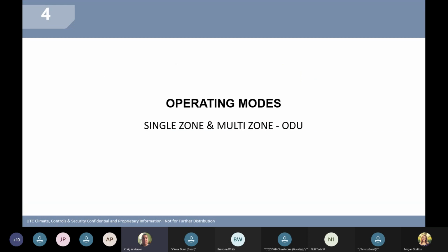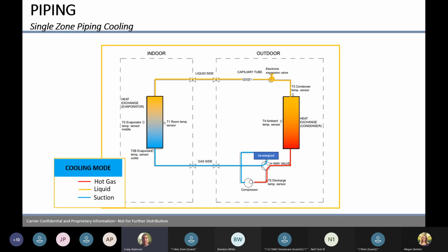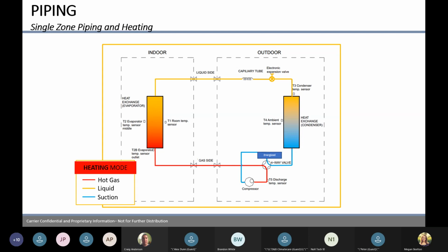So operation modes for our single zone and multi-zone. It's just a couple diagrams of how you're looking at an indoor unit and outdoor unit. So we're looking at a single zone. Our coil is de-energized. It's not being energized, so we're in cooling mode. How the gas is flowing to the indoor unit to the outdoor unit. Just a simple picture of how your gases are going to be flowing.